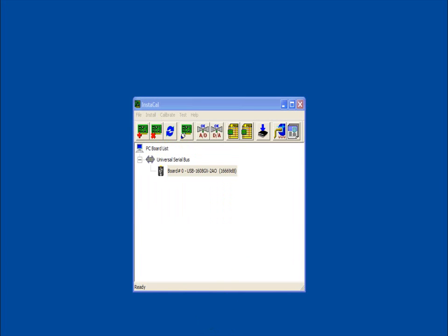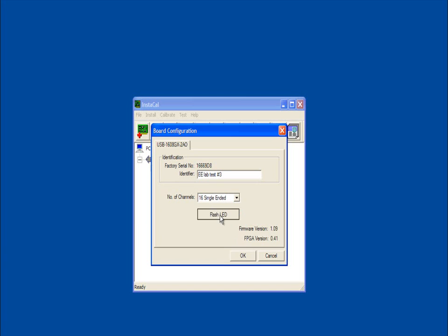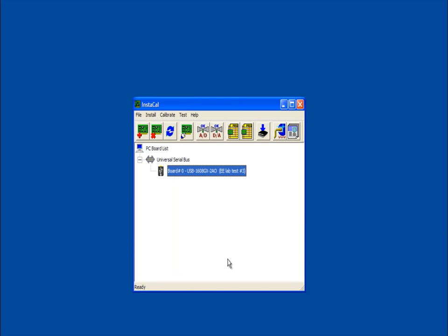To configure a measurement computing device using Instacal, double-click on the device in the main Instacal window to open the board configuration dialog box. Most MCC devices support analog inputs, which you can configure using Instacal. In this example, a text identifier of EELab test number 3 is entered. The device configuration is changed from 8 differential to 16 single-ended analog input channels. To test USB communication, click the Flash LED button to verify that the device LED blinks. Click OK to close the dialog box and save your settings.